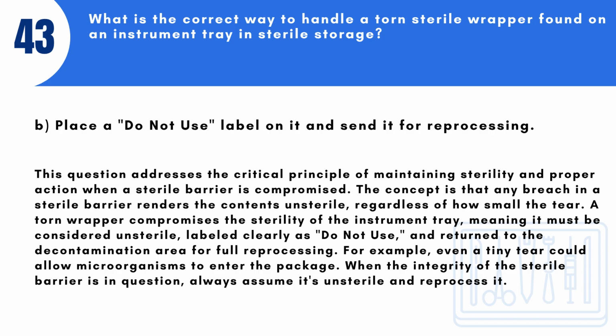This question addresses the critical principle of maintaining sterility and proper action when a sterile barrier is compromised. The concept is that any breach in a sterile barrier renders the contents unsterile, regardless of how small the tear. A torn wrapper compromises the sterility of the instrument tray, meaning it must be considered unsterile, labeled clearly as do not use, and returned to the decontamination area for full reprocessing. For example, even a tiny tear could allow microorganisms to enter the package. When the integrity of the sterile barrier is in question, always assume it's unsterile and reprocess it.